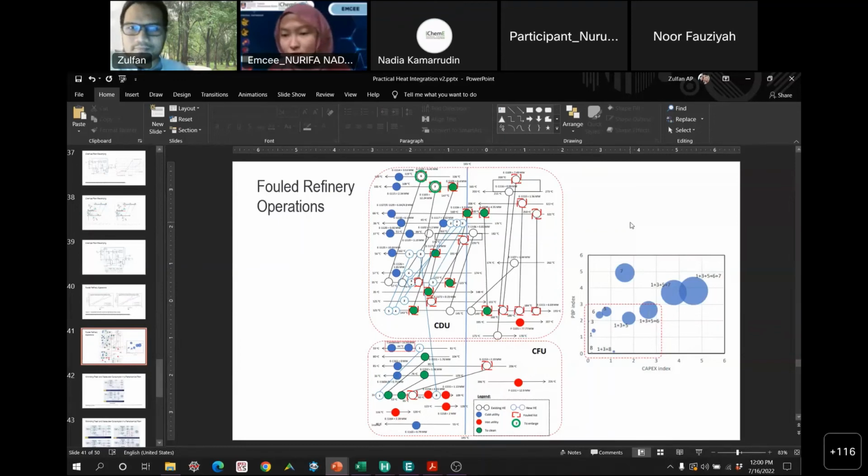The next question is regarding the project where you identified the faulty heat exchanger. How do you determine it is faulty based on the overall heat transfer coefficient? Very good. This is not something that they teach you in class. Obviously, in heat transfer class, you learn about the overall heat transfer coefficient, the U value. This coefficient is something that is found in the field. It's not something that you calculate.